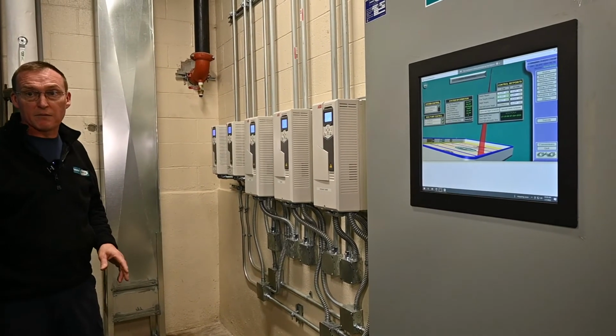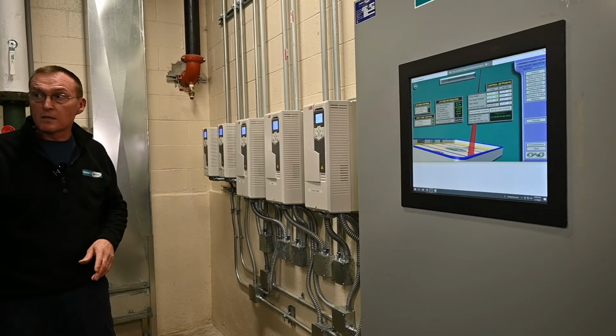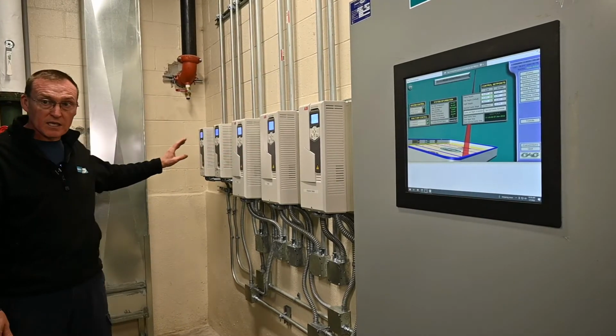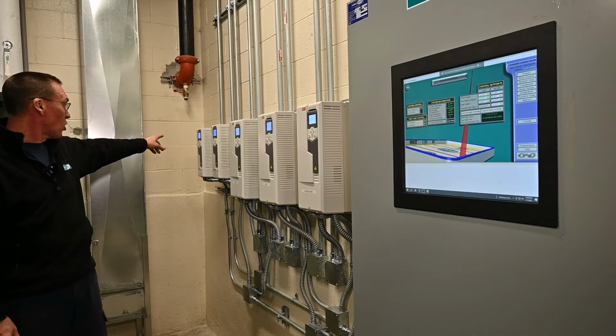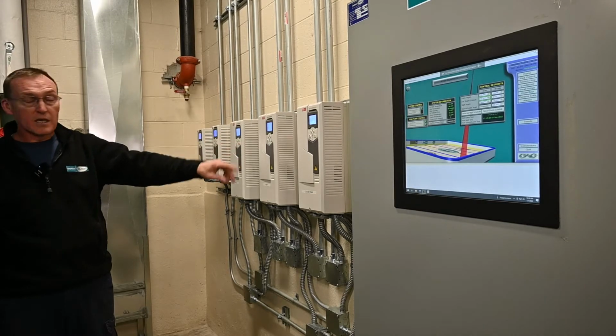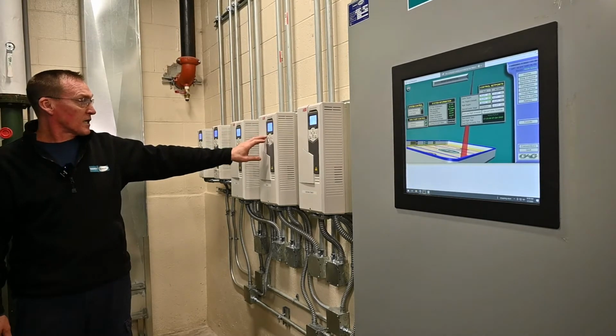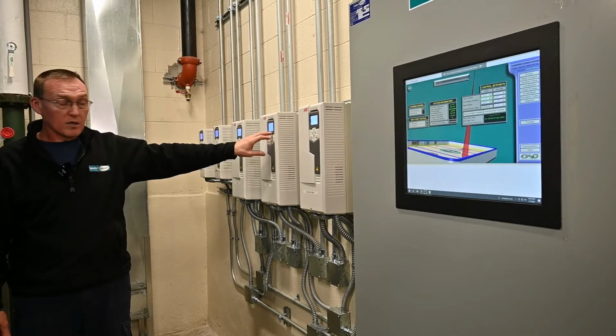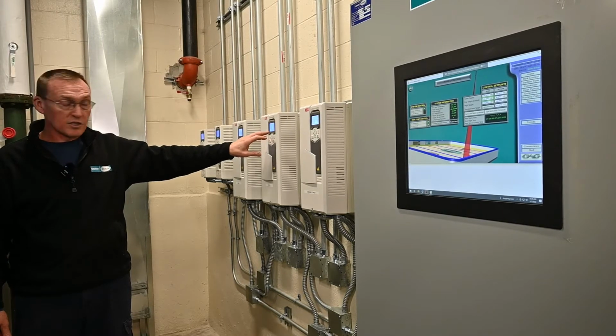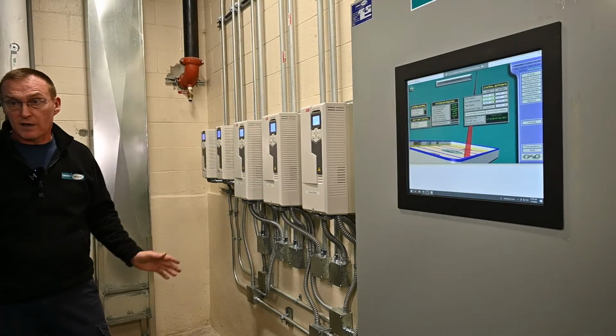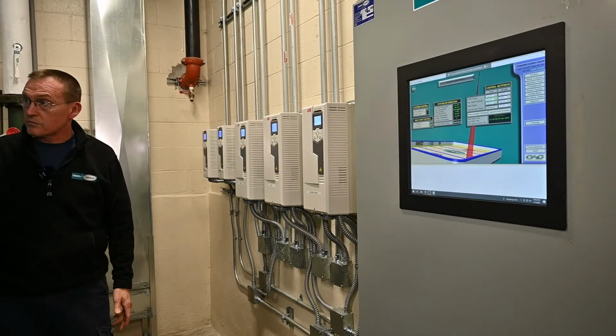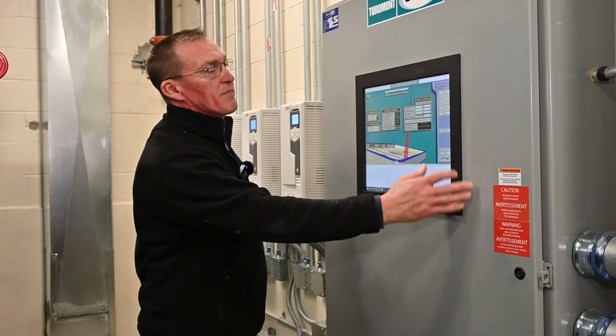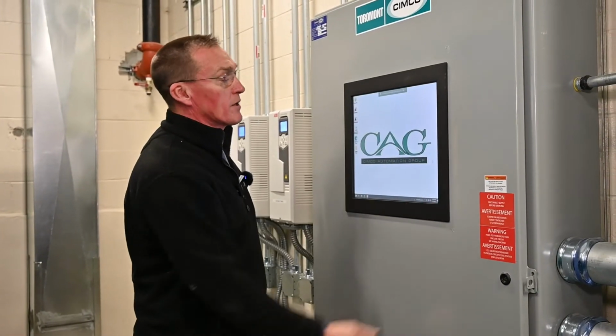If you have a power failure, it's always a good idea to come down here and double-check the VFDs and make sure that they all have green lights. If not, read the screen, it'll tell you whether or not you can reset, and it'll be one of these buttons here. And it'll just say reset, boom, everything will be fine, and restart and good to go, okay? So in here, I'm just going to quickly log out.